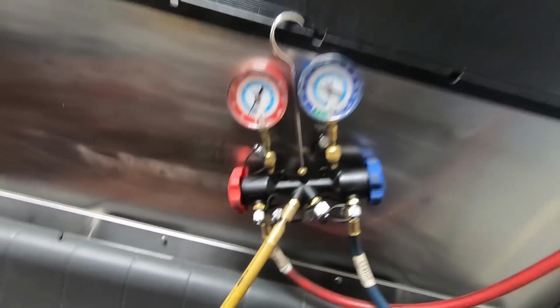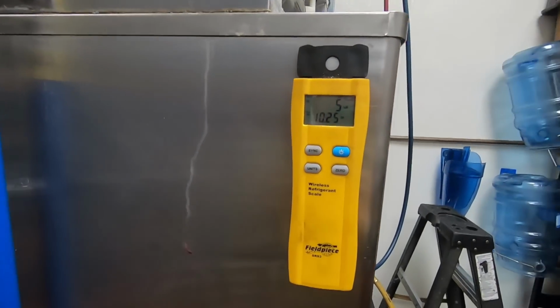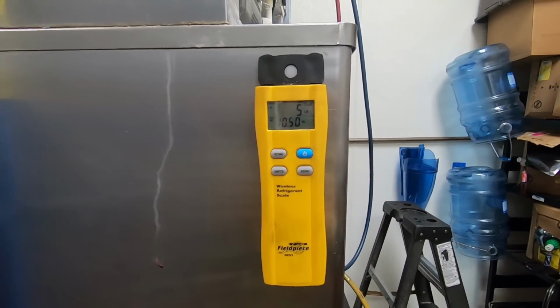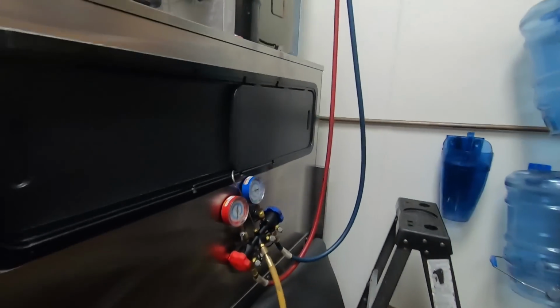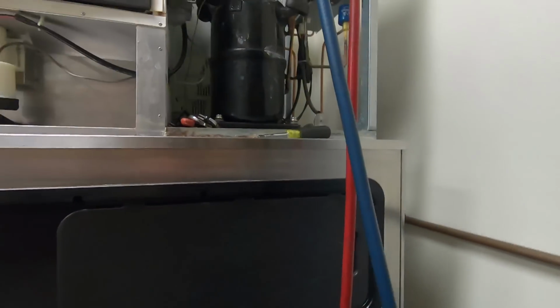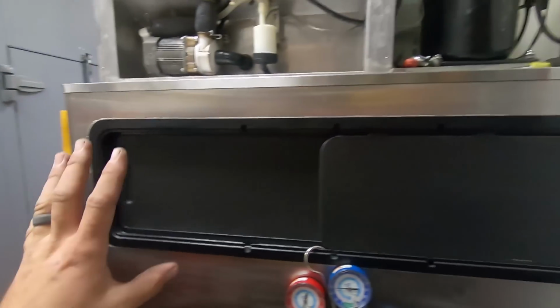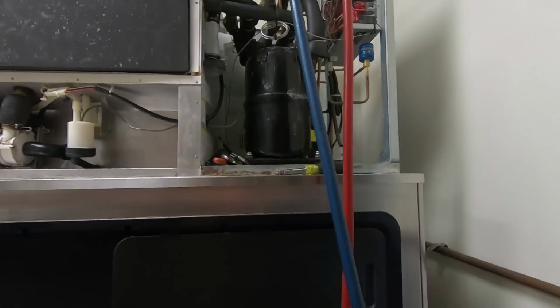So now we're just waiting, waiting for this guy to recover, seeing where we're at right now. The true test will be, does it have the factory charge in it, or is it actually low? We know it's low, but you want to pay attention, look at the big picture. As I'm recovering the gas, if all of a sudden it has the factory charge, then I need to figure something out, something's going wrong.